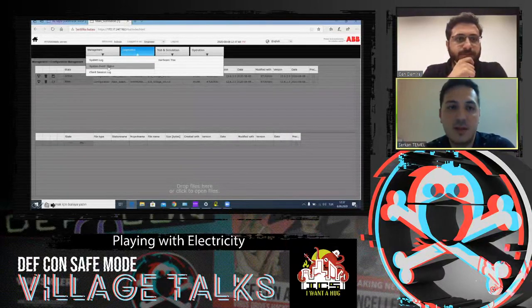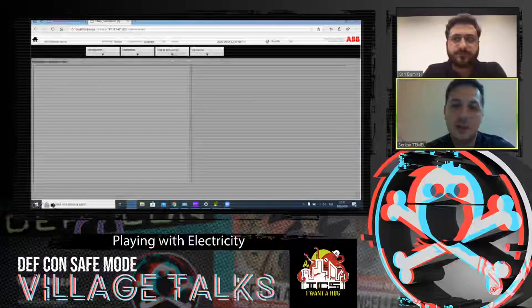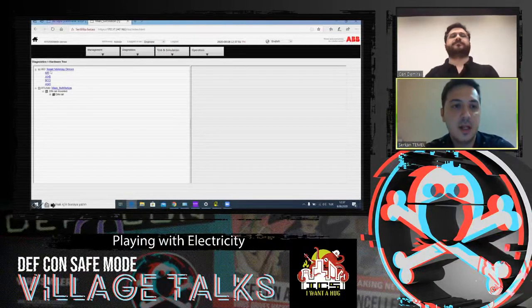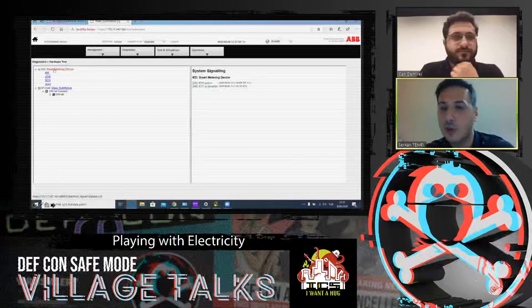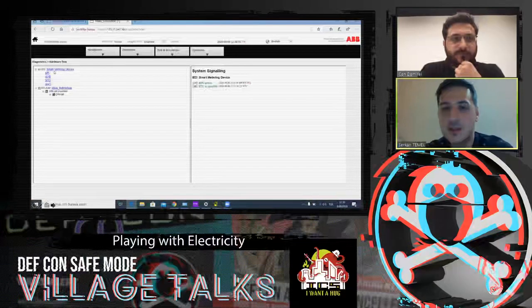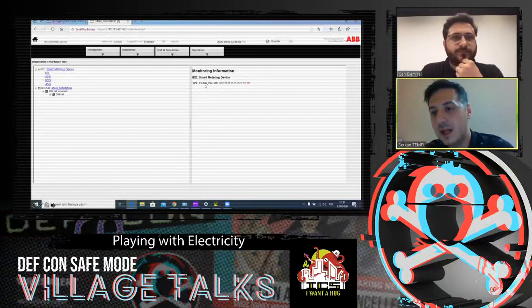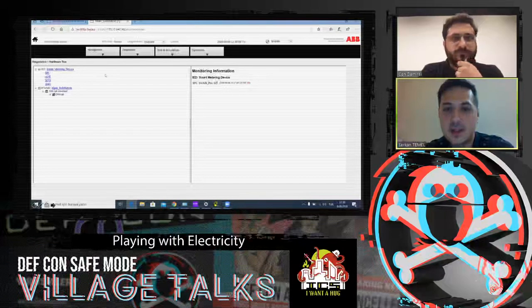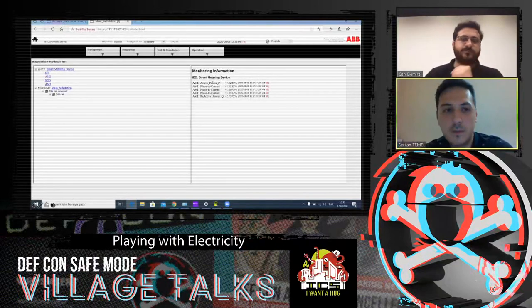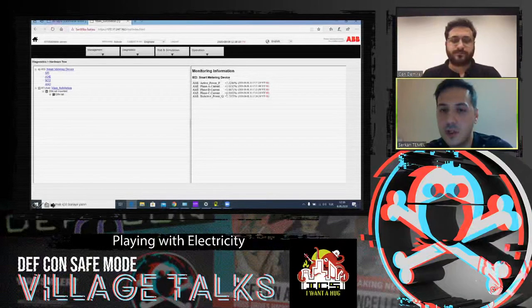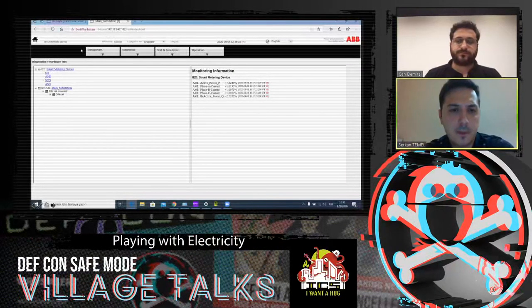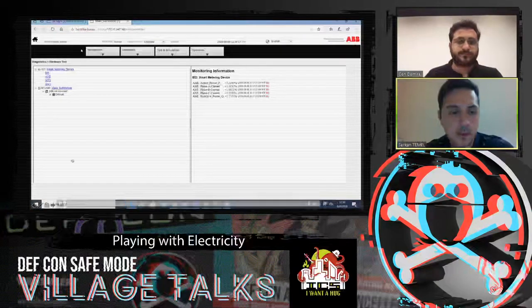Also directly on the site, you can easily monitor signals, system log, system event status, and client session log, and also the hardware tree. The hardware tree is live monitoring about the RTU. You see that the RTU is active. The RTU is operable, which means it's connected to the IED device. As you see, the circuit breaker switch position is on, and also metering information about the system. It is live data, real-time data.